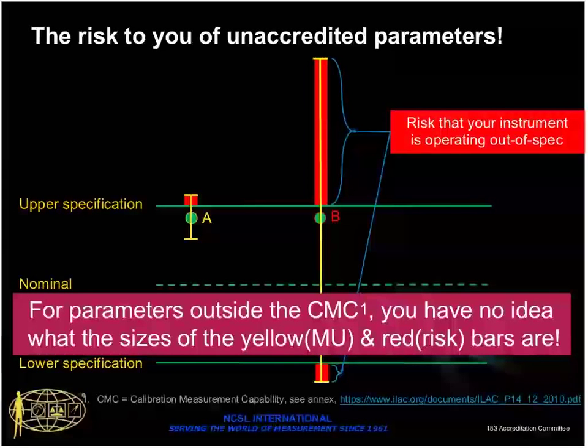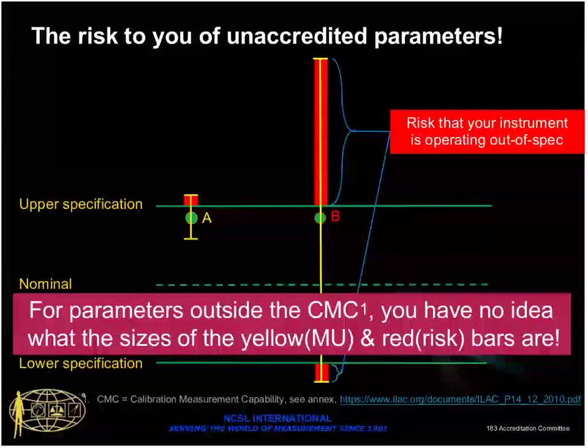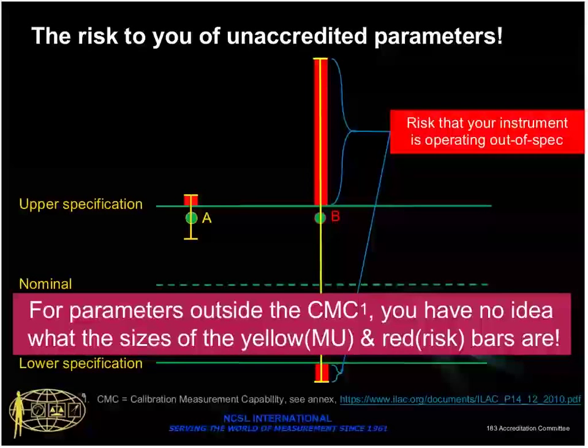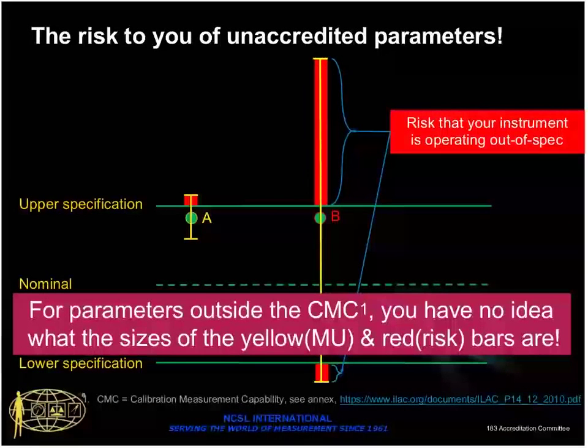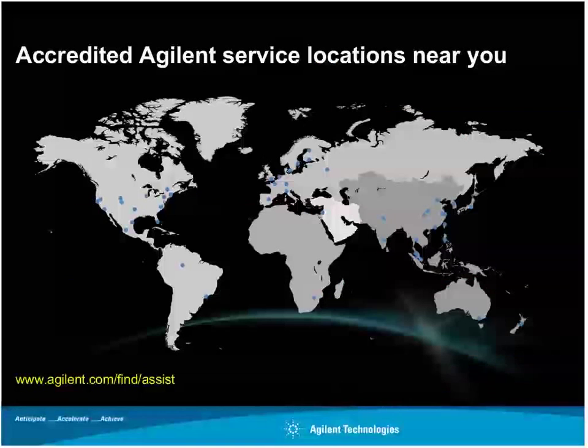Now, I know human nature well enough to know that when any lab has really good measurement uncertainty, for example, as what's shown over in case A here, then no self-respecting metrologist would slow down. They would tell the assessor, by all means, accredit us for that parameter. On the other hand, if you have older instrumentation, and oftentimes even something as new as 10 years ago, the block diagrams of all of our spectrum analyzers, for example, have completely digital IFs now, and the accuracy that they have is incredible compared to even just a few years ago. So if you're calibrating a signal generator, for instance, and you're using one of our spectrum analyzers as a receiver, you need the very latest ones, because those are the ones with the block diagrams that are going to give you the kind of measurement uncertainty that you see on the left. And other ones would be quite a bit more. So it's definitely something to think about.